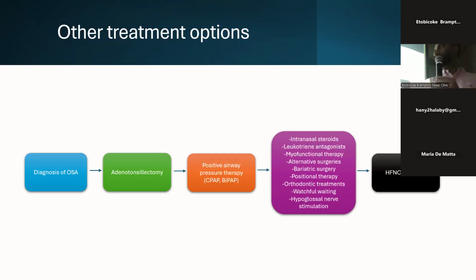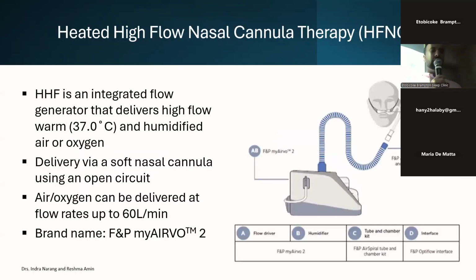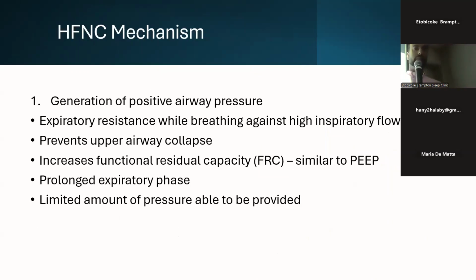But where does high flow therapy come into play here? So what is high flow therapy? High flow therapy is basically a device that provides high flow and warmed air or oxygen, and it's delivered primarily with a soft nasal cannula through an open circuit, although there are other interface options available. Depending on the size of the cannulas, it can provide up to 60 liters per minute. The more common model that we see is a MyAirvo 2, although there is a MyAirvo 3 now as well. This is what the setup looks like. The mechanism is very important when we think about why high flow could be beneficial in pediatric patients.